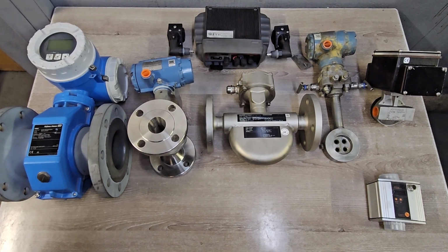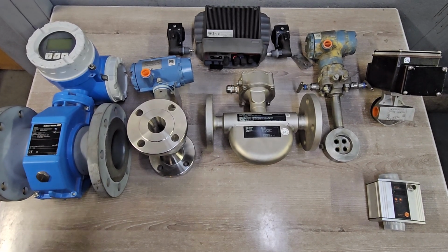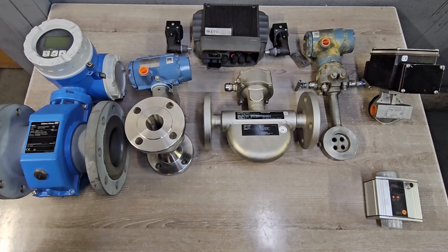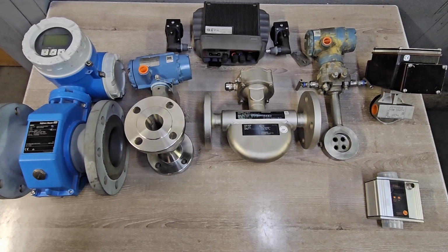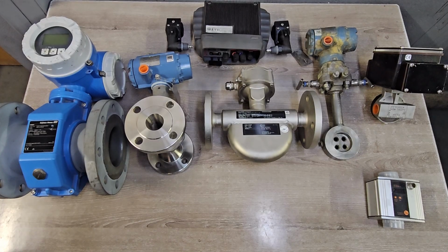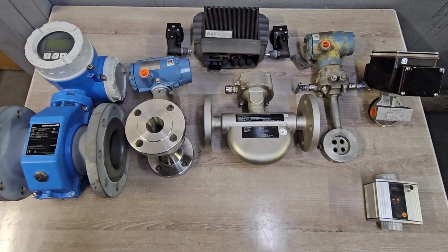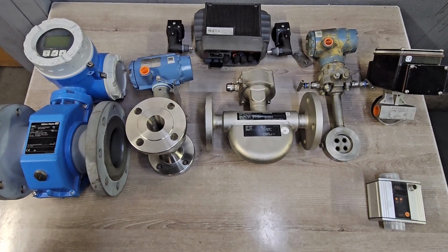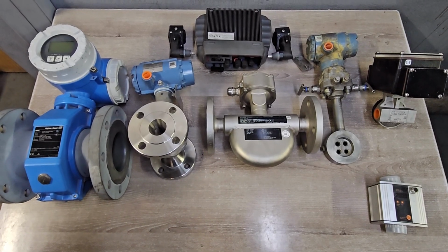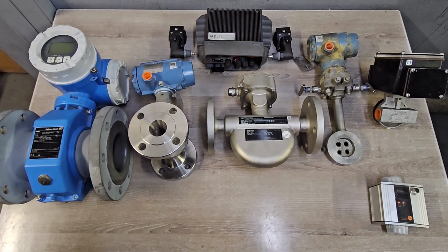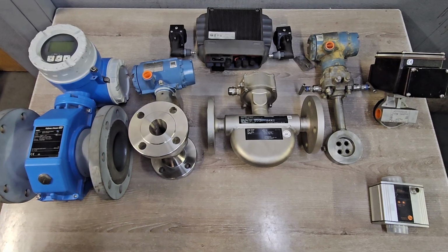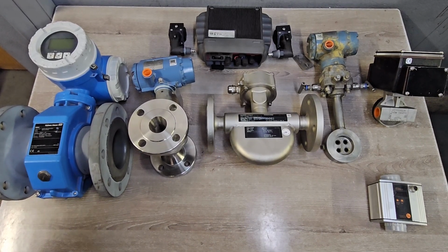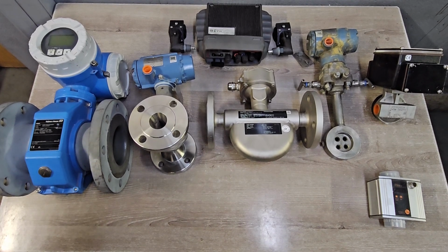So when there is flow in the tube, in between the two electrodes, it will cause a very small distortion. It would be very difficult for a human being to see that distortion. But those sensors are so sensitive that even a small distortion, they can detect it, and then it gets amplified to a current signal and then sent to a DCS system or a PLC system in the form of a 4 to 20 milliamp signal.